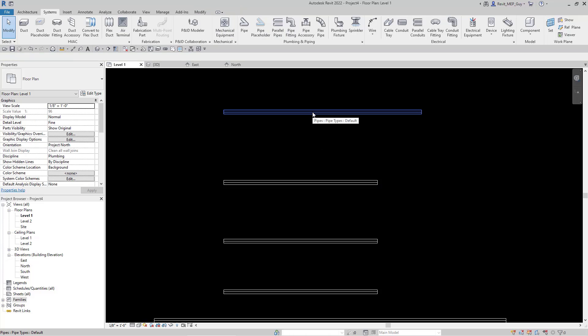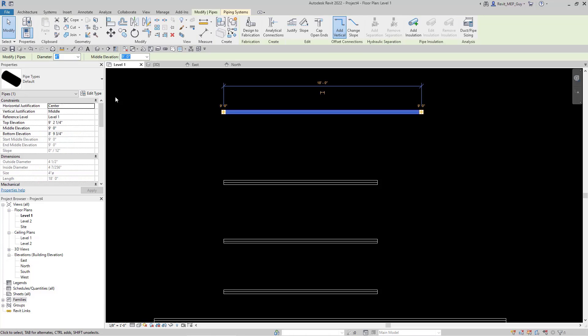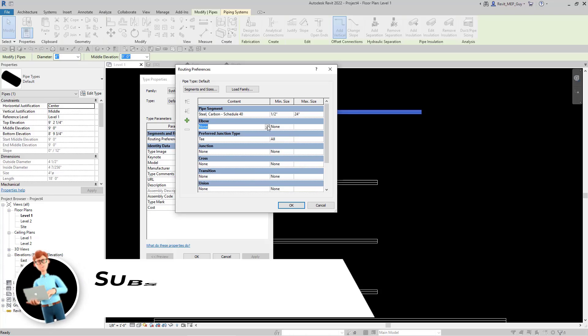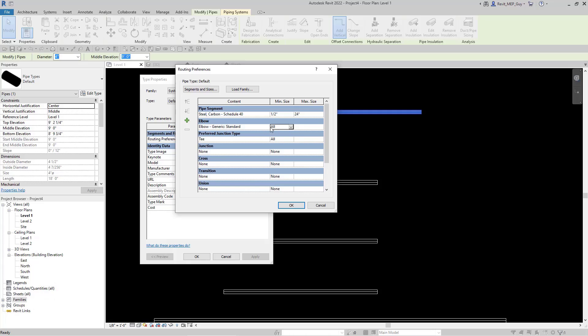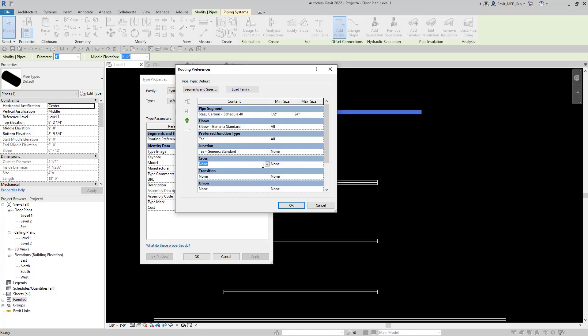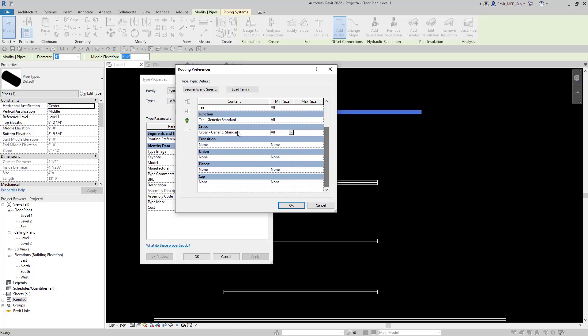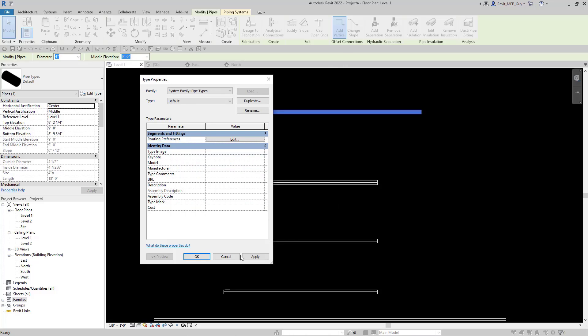The way to attach fittings to a certain pipe is to click on the pipe, go to Edit Type, go to Routing Preferences and hit Edit. Now I have to select all the elbows I want to use — for Elbow I'll use Generic Standard, and for minimum size I'll select All. For T or Junction I'll use this T generic standard. For Junction I'll use T Generic Standard, and for Cross I'll use Cross Generic Standard. I have to do this for all fittings and make sure I select All sizes. As you can see, this is taking quite a bit of time and I don't really want to have to do this — so I'm going to show you a better way.